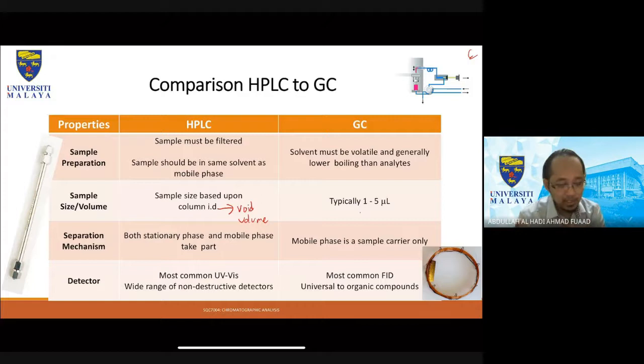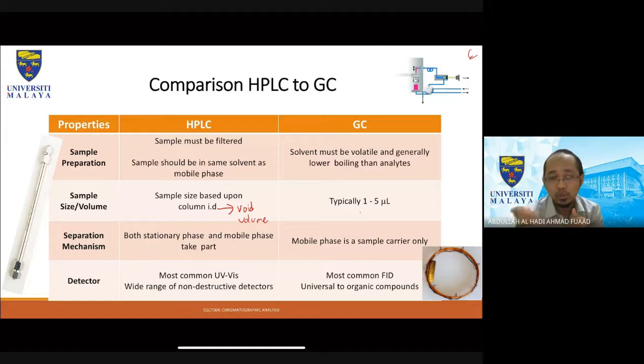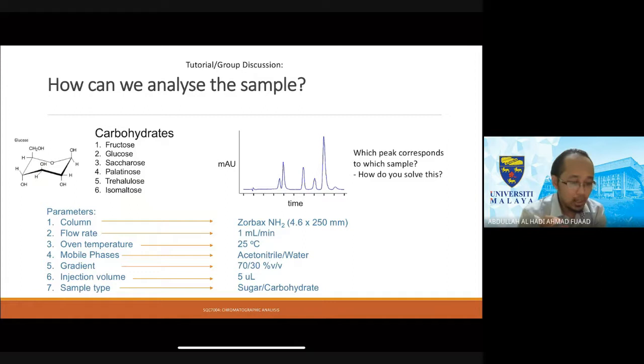For detectors, the most common one attached to HPLC is the UV-Vis detector. You can also have PDA — different types of UV-Vis detectors. It is a wide-range, non-destructive detector, which is why it is widely used. For GC, the most common detector is FID, which is universal for all organic compounds, making it ideal for organic compound analysis.